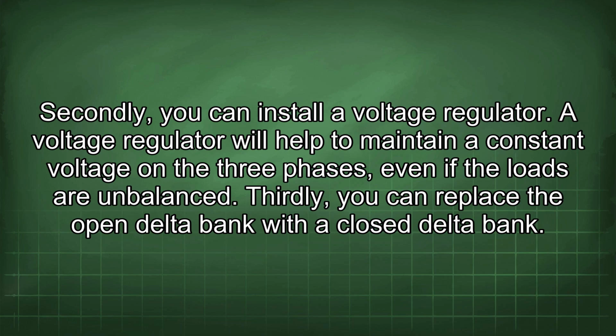Secondly, you can install a voltage regulator. A voltage regulator will help to maintain a constant voltage on the three phases, even if the loads are unbalanced. Thirdly, you can replace the open delta bank with a closed delta bank.